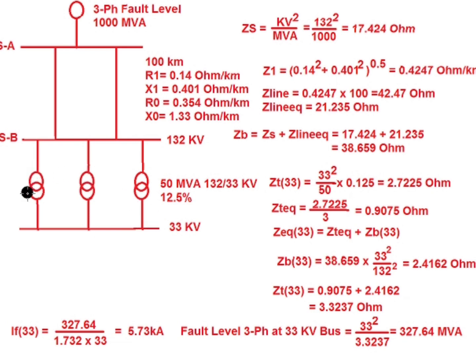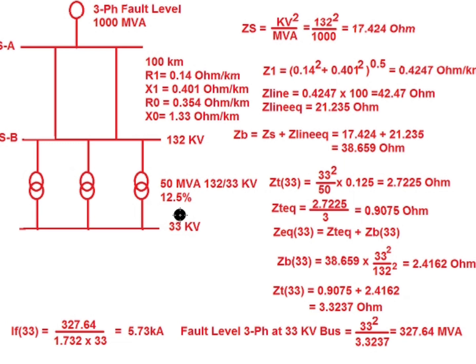For the transformer: three transformers are running in parallel, each with a percentage impedance of 12.5%. The impedance seen at the 33 kV side for each transformer is: ZT33 = kV² / MVA × percentage impedance = 33² / 50 × 0.125 = 2.7225 ohm. Since three transformers are running in parallel, the equivalent transformer impedance is: ZT_equivalent = 2.7225 / 3 = 0.9075 ohm.